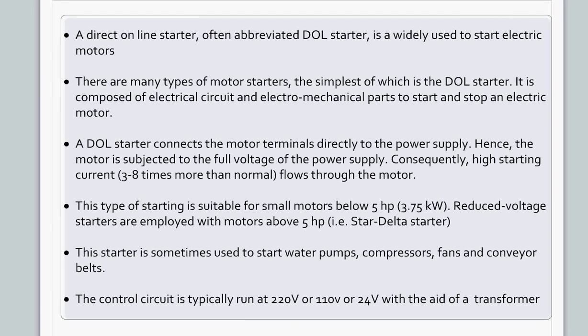So direct online starter is also known as a DOL starter and widely used to start electric motors. There are many types of starter, but the simplest one is DOL. It is composed of electrical circuit and electromechanical parts to start and stop the electric motor. In a DOL starter, it connects directly to the power supply, so the motor gets the full voltage, and initially it can draw high current, 3 to 8 times more than the normal current.